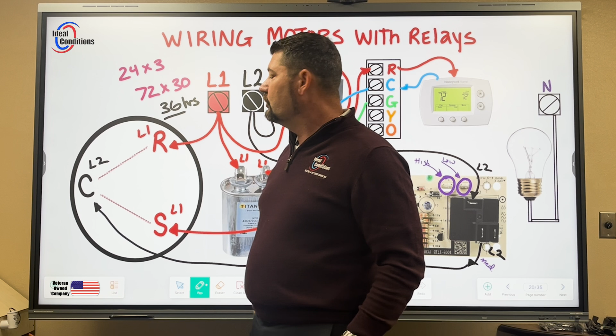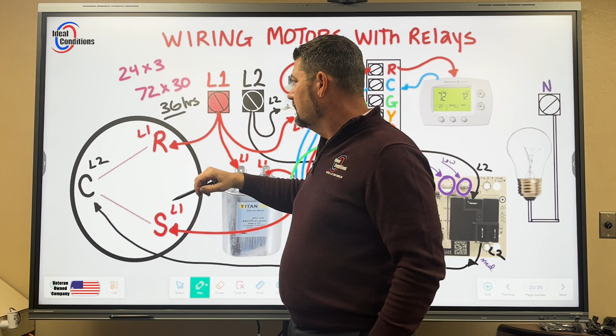Your compressor shut off and left the blower running by design, because we lost the G call, we lost that Y and O call right on that heat pump, or that Y call on that straight cool. But this stayed in circuit for 1 extra minute. 3 times an hour, that's 3 minutes an hour, 24 hours. That's 72 minutes a day over 30 days, which is 1 month. Comes up to 2,100 something minutes. Divide that over 60 minutes an hour, and it comes up to 36 hours in 1 month.